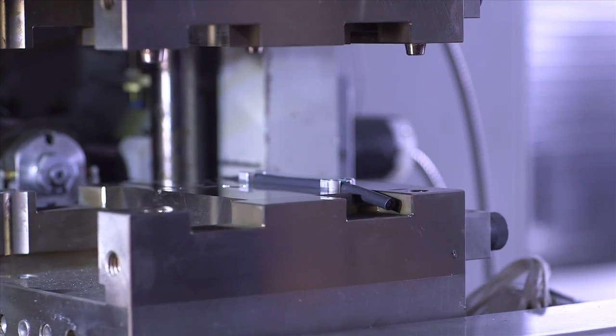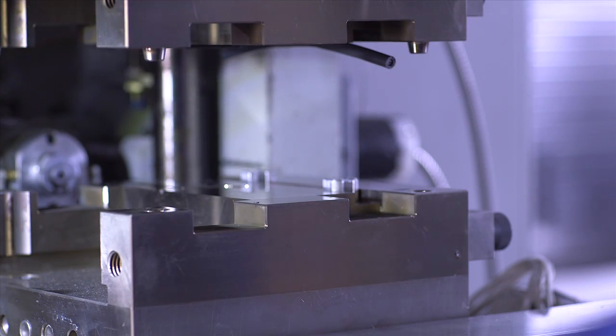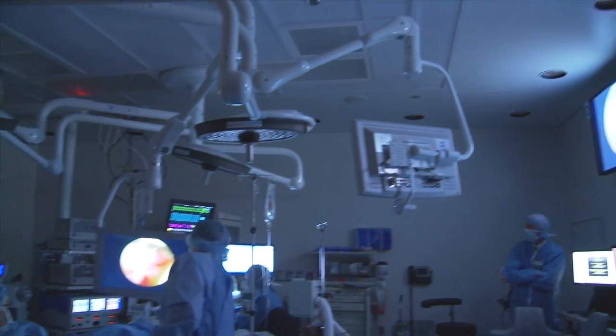Connectors and silicone jacketed cables are overmolded with silicone to achieve a strong bond between them and assure a high level of sterilization withstand. This enables the cables to be used in surgical applications, where demanding cleaning and disinfection methods are used.